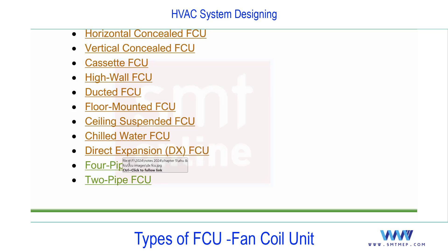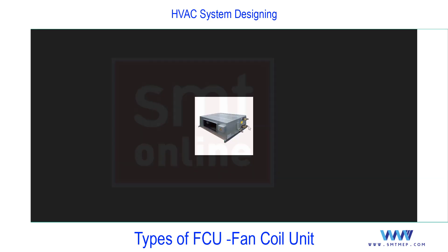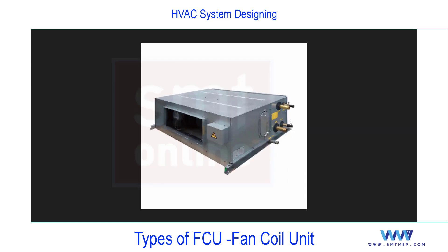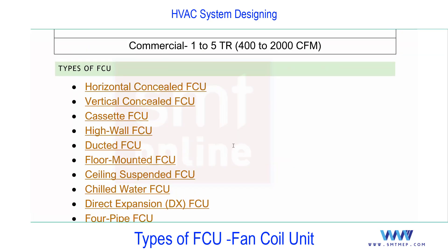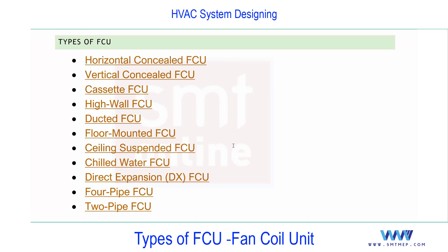A two-pipe FCU has one shared coil for either cooling or heating. A four-pipe FCU has separate coils — one cooling coil connected to the chiller and one heating coil connected to the boiler — allowing independent use of each as required. This makes the four-pipe system more flexible for year-round conditioning.